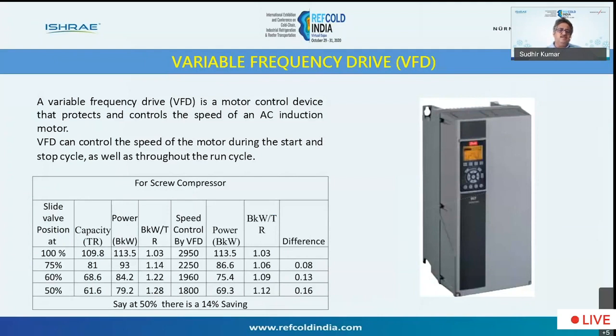But if you see in this chart below, you will find that at 75% slide valve position, capacity is at about 1.14 BKW per TR as compared to the 100% load of 1.03. Whereas in a VFD system, by speed controlling, we can get the same capacity at approximately 1.06. So you are getting a difference. The lower the slide valve position, the better the power saving you get with a variable frequency drive.